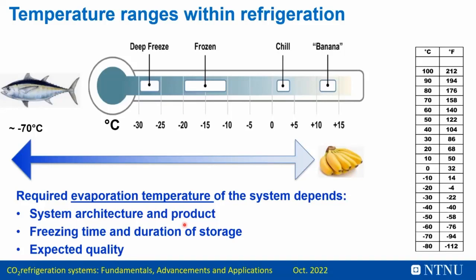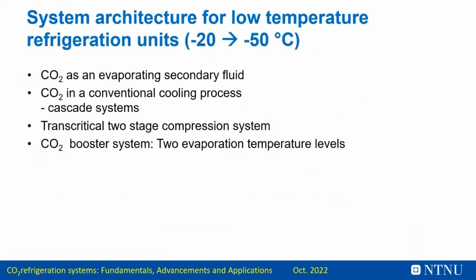And as I showed you just before, it is very interesting to have very low temperature application with CO2 because you can have a very uniform temperature across your heat exchanger, which is interesting on blast freezers or freezing tunnels and so on. And the lower the temperature, the lower the freezing time, and the duration for the storage is very important for what kind of evaporating temperature we should utilize and what kind of quality do we want. So now I would like to go into a system architecture for low temperature refrigeration units, maybe from -50 up to -20, in that range.